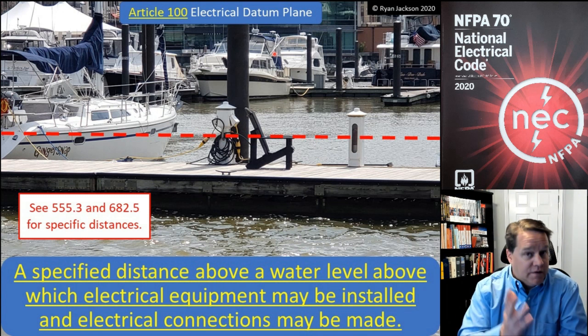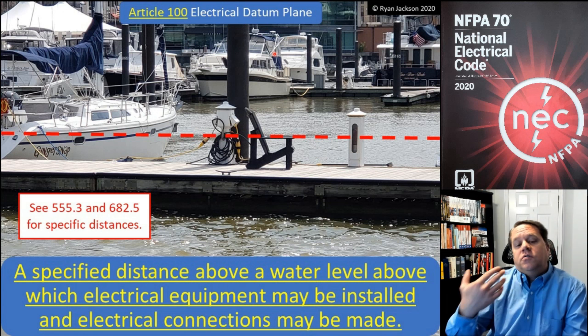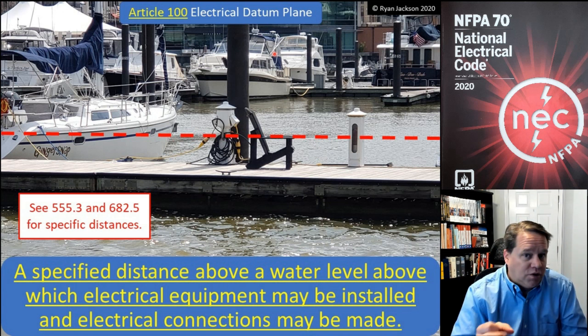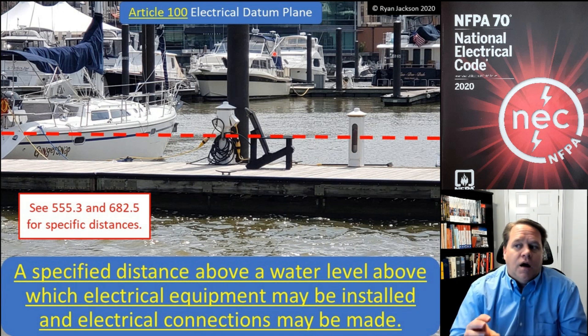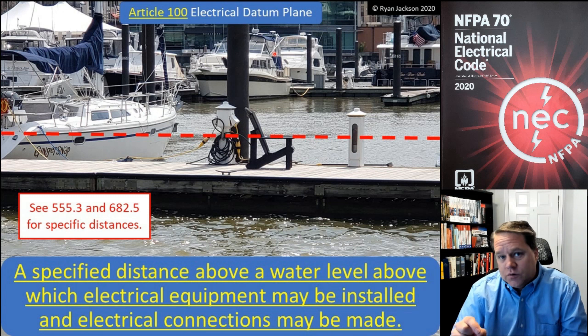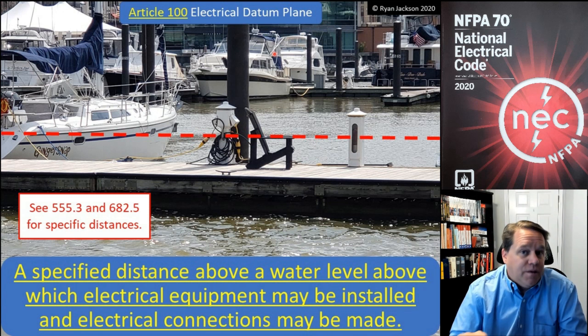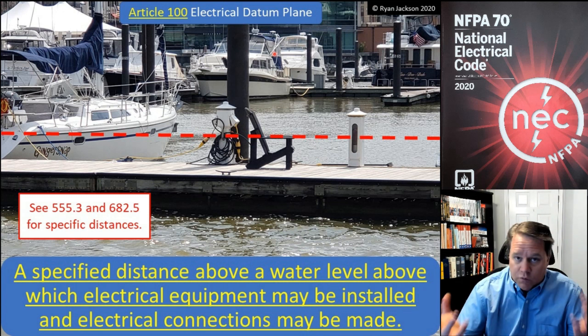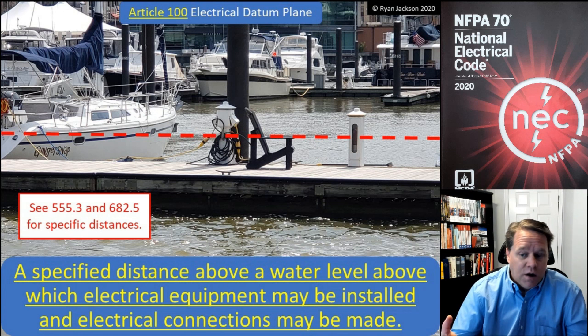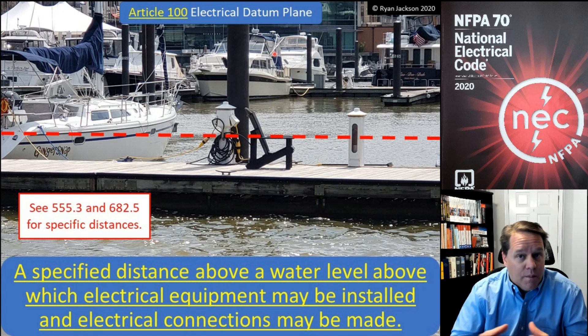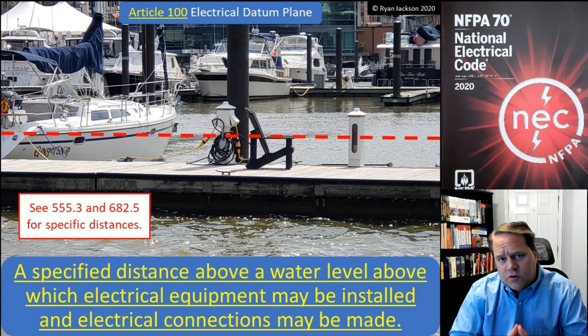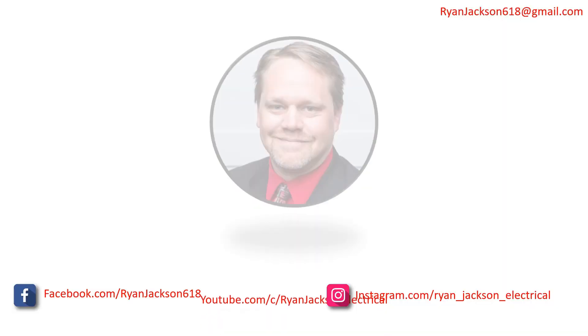Exactly where the datum plane is depends on those other factors — you'd want to go to 555.3 or 682.5 to determine where the actual electrical datum plane is. In the 2023 code, it looks like we're going to add electrical datum plane to article 551, which covers RV parks as well. This makes sense if you have an RV park next to a river or the ocean, where you need to establish where you may and may not have electrical equipment and terminations.